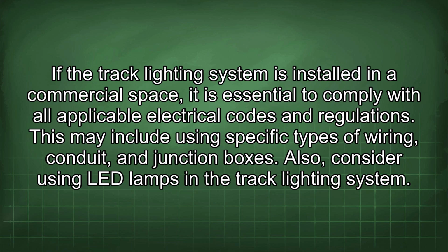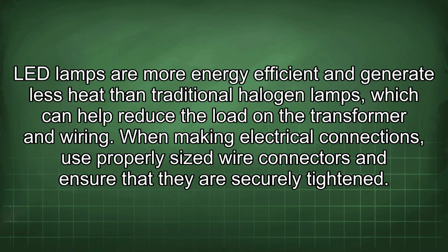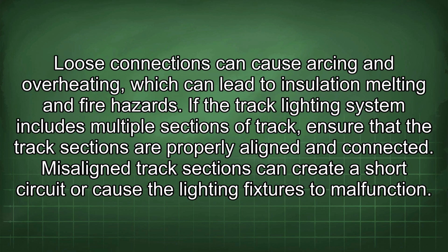Also, consider using LED lamps in the track lighting system. LED lamps are more energy efficient and generate less heat than traditional halogen lamps, which can help reduce the load on the transformer and wiring. When making electrical connections, use properly sized wire connectors and ensure that they are securely tightened. Loose connections can cause arcing and overheating, which can lead to insulation melting and fire hazards.